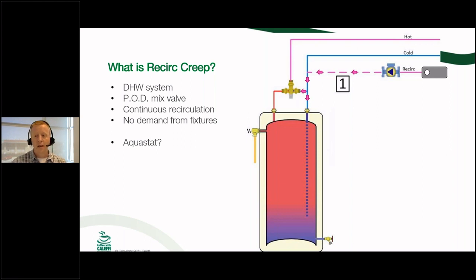And I would say the biggest thing that we're talking about going forward in the future here is by turning off that recirc, you are creating a perfect breeding ground for Legionella bacteria. Okay, and we keep hearing about Legionella over and over again, whether it be cooling towers or domestic hot water systems, potable water systems, things like that. But Legionella bacteria is looking for not only warm water typically, but it's looking for stagnant water. So if you are running that recirc on a timed event, you know, to where during unoccupied times it's shutting off, or it's on an aquastat, again, you're creating that perfect breeding ground, because the Legionella bacteria is looking for that 70 to 120 degree water, and it's looking for stagnant water. And again, stagnant is the key term here. So by keeping that recirc on, you can eliminate that stagnant water scenario, and you can help to basically kind of manage that Legionella risk to an extent.